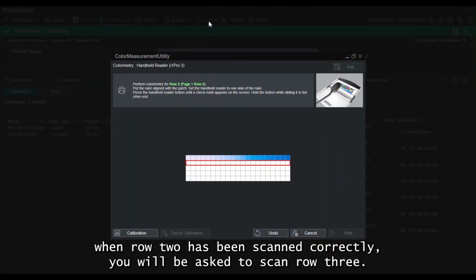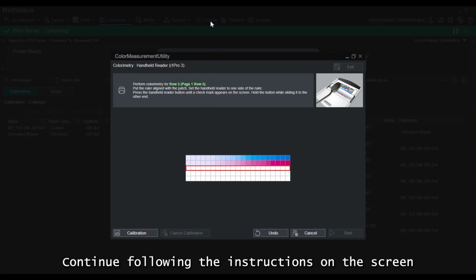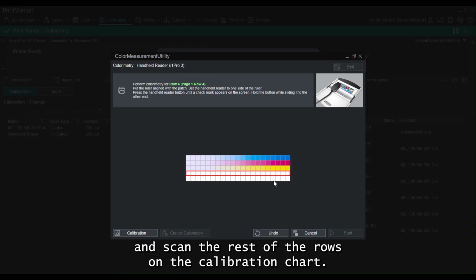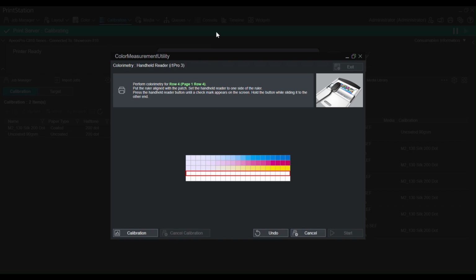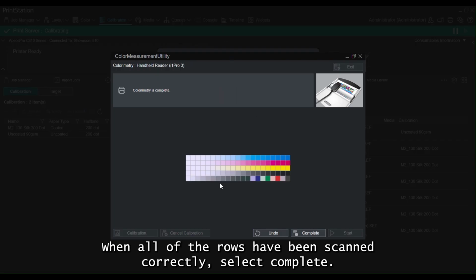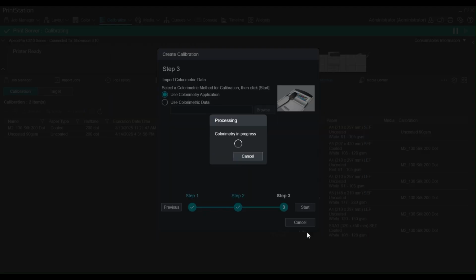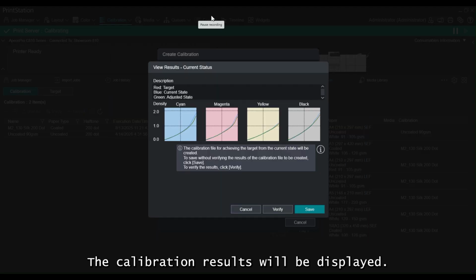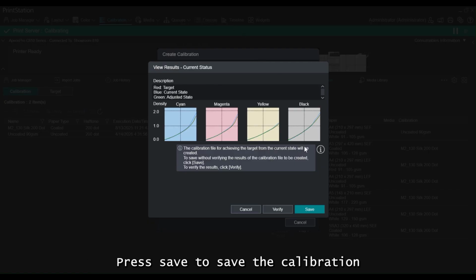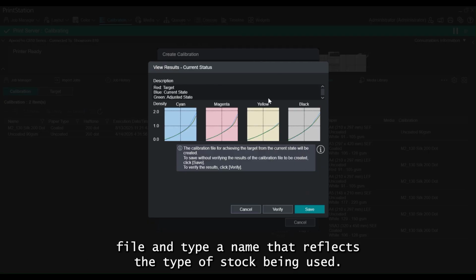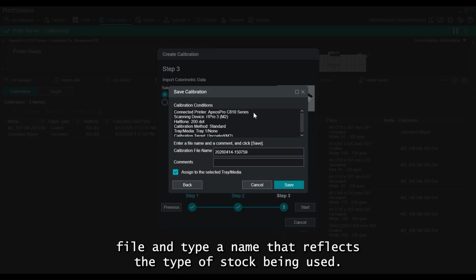When row 2 has been scanned correctly, you will be asked to scan row 3. Continue following the instructions on the screen and scan the rest of the rows on the calibration chart. When all of the rows have been scanned correctly, select Complete. The calibration results will be displayed. Press Save to save the calibration file and type a name that reflects the type of stock being used.